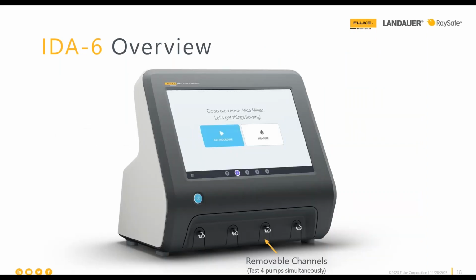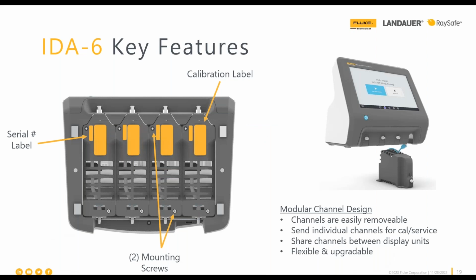Now, looking at the physical device itself, it does have a 10-inch high-resolution touchscreen. There are 4 channels that are removable, as we touched on earlier. Next slide, please. If you look here, this is the bottom side of the device. On the left, you have the 4 individual channels, and it's very simple to remove those for calibration and or repairs. It's just 2 simple mounting screws. It does have the ability to remove them, so you can send in the individual channels. If you have multiple displays and multiple channels, you can swap channels between displays.